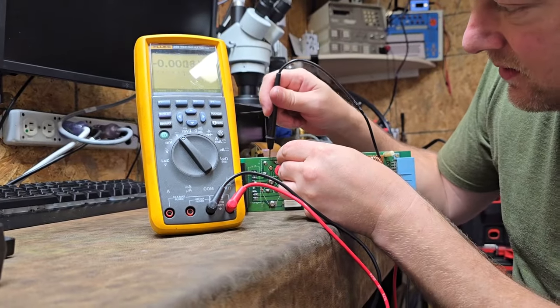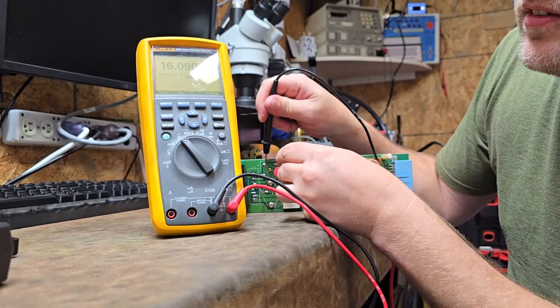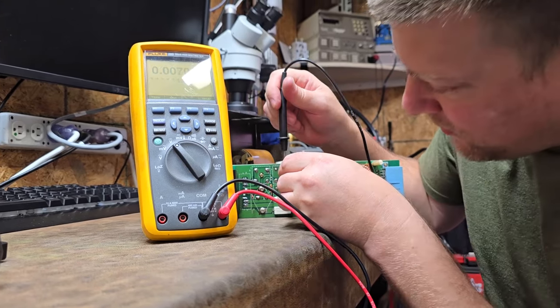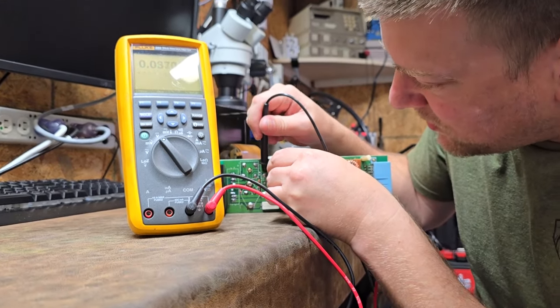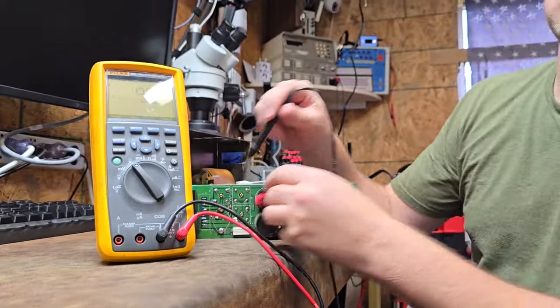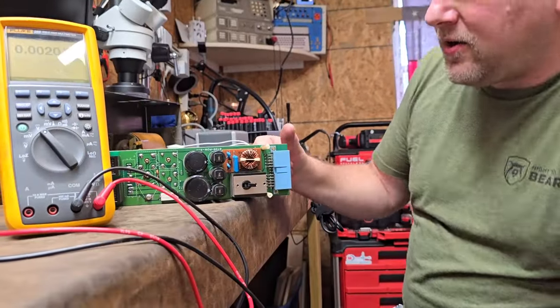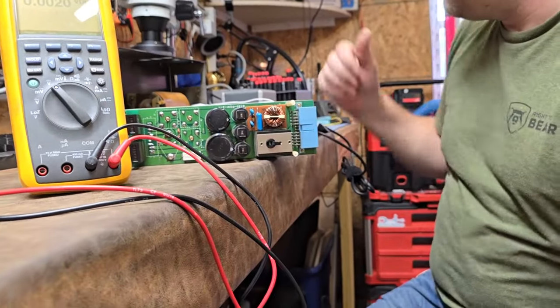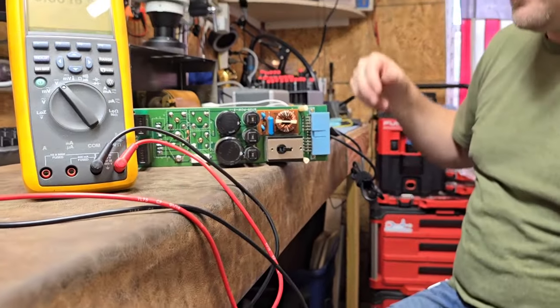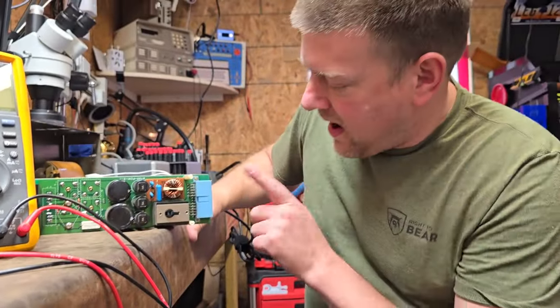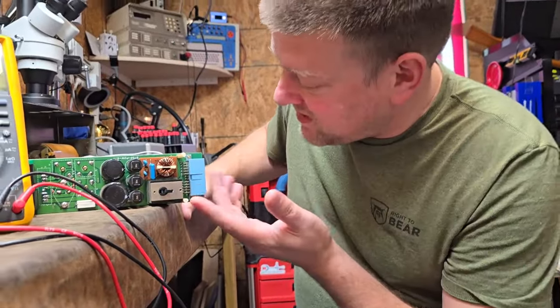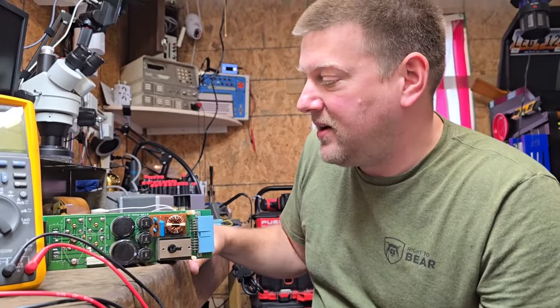Now let's go ahead and let's go to the next one - 16 volts DC. All right, I don't know if those are within tolerance but good enough. And this one here, I got 31 volts DC. So I currently have three different DC power rails. I'm going to go ahead and shut it off. So on these pins, whichever pins they are, should be my DC rails to turn the machine on, and from all I can see that is accurate.